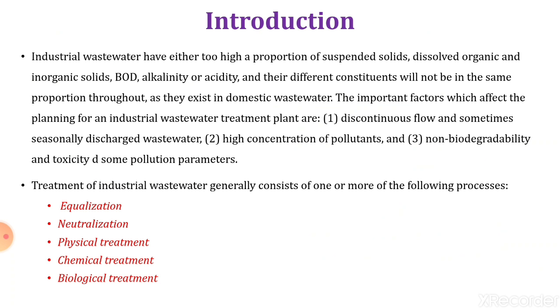Industrial wastewater may have either too high a proportion of suspended solids, organic and inorganic solids, BOD, alkalinity, or acidity, and their different constituents will not be in the same proportion throughout as they exist in domestic wastewater. The important factors which affect planning for an industrial wastewater treatment plant are discontinuous flow, sometimes seasonally discharged wastewater, high concentration of pollutants, non-biodegradability, toxic substances, and some pollution parameters.